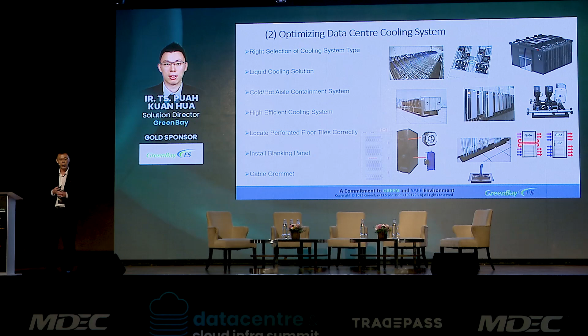This is one of the cooling trends we can see now. Previously it used to be uncontained rooms, but with higher rack density, clients will go for containment systems. What if power density goes beyond 35 to 40 kilowatt per rack or even higher? Liquid cooling will be one of the solutions to tackle these high density IT racks and also give a better PUE.